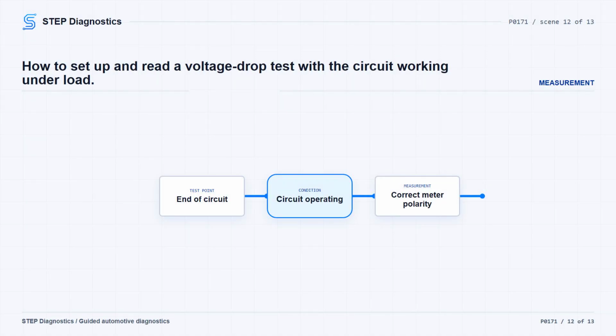For voltage drop testing, connect the voltmeter at the beginning and end of the suspect circuit and test with the circuit operating or attempting to operate, with power available to flow. Keep meter polarity aligned with conventional current flow. A 0-volt reading during voltage drop testing can mean poor voltmeter connections or that the component has not been turned on. Voltage indications greater than 0.5 volts indicate abnormal voltage loss and point toward high resistance in wires or connectors.